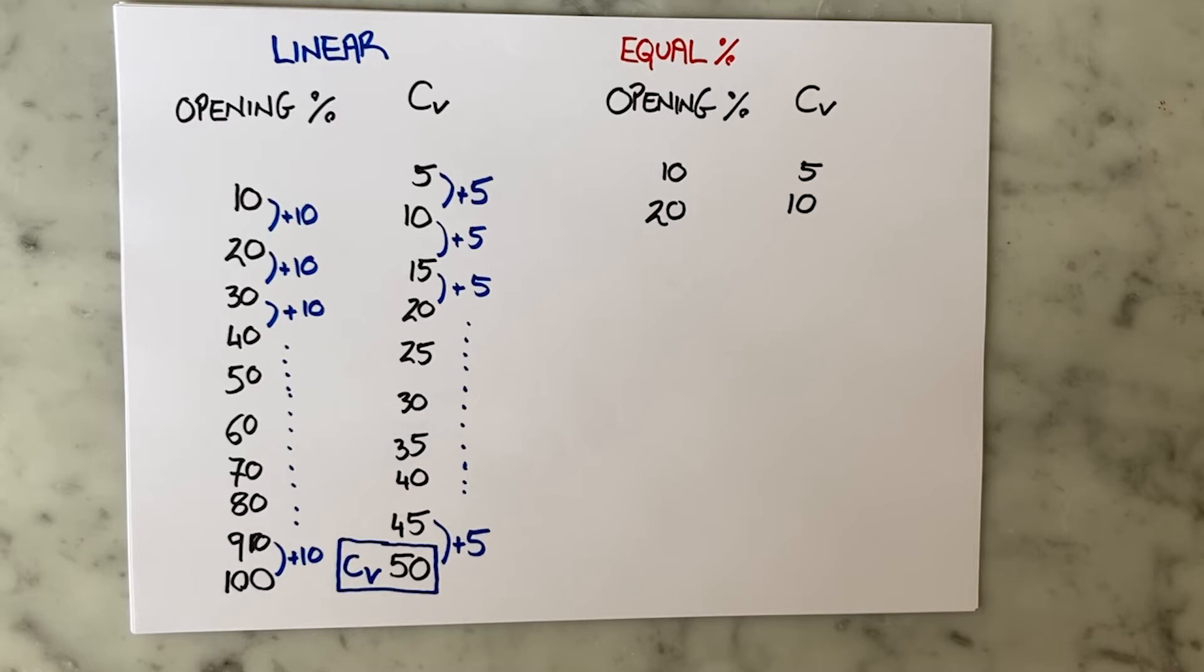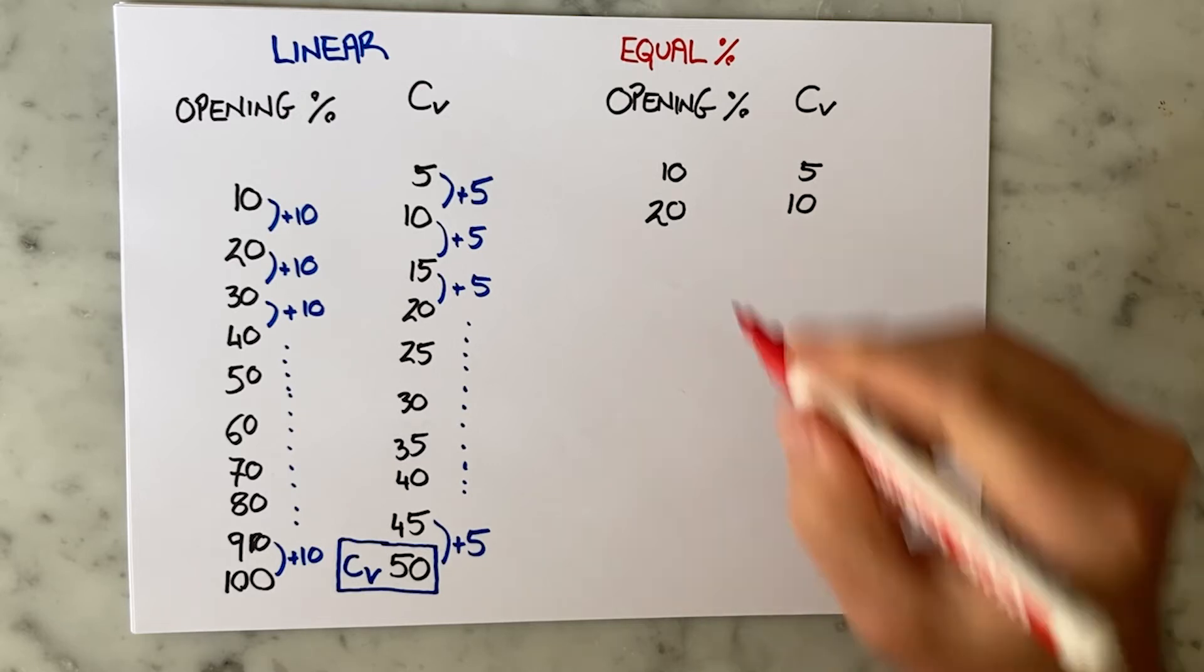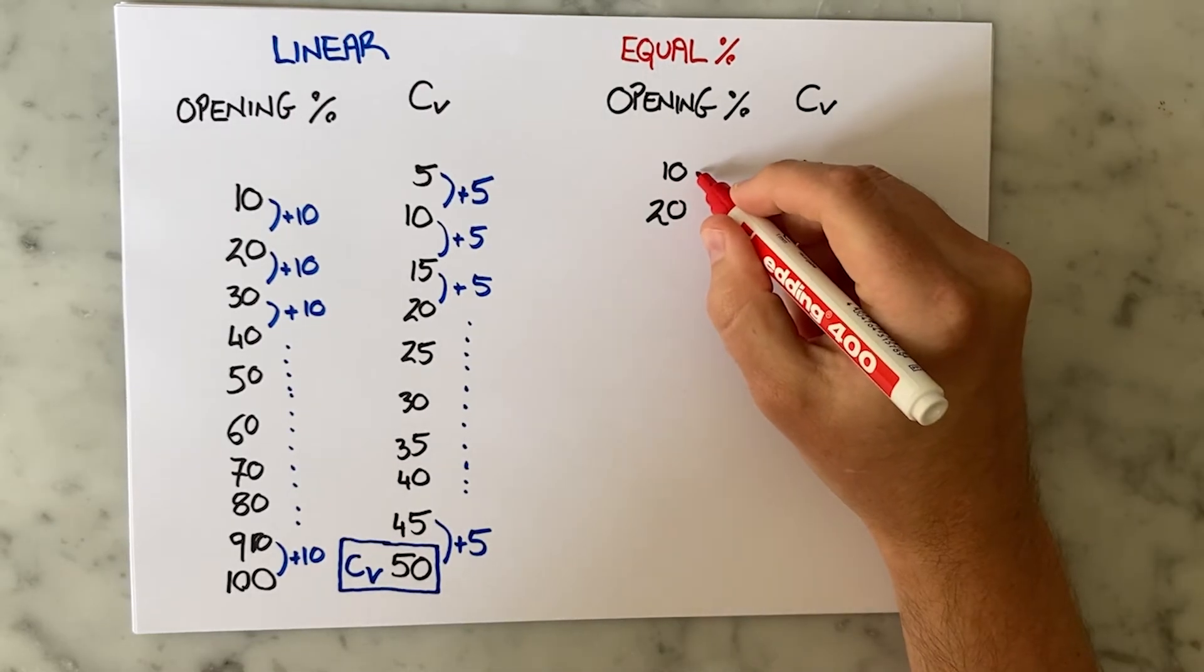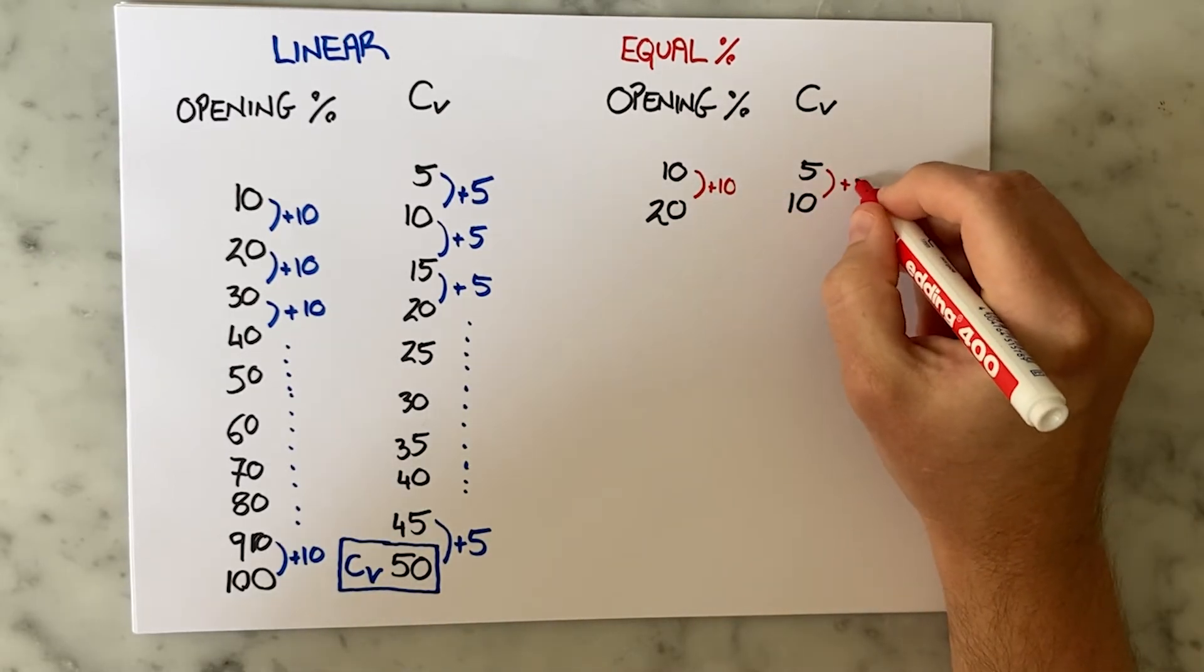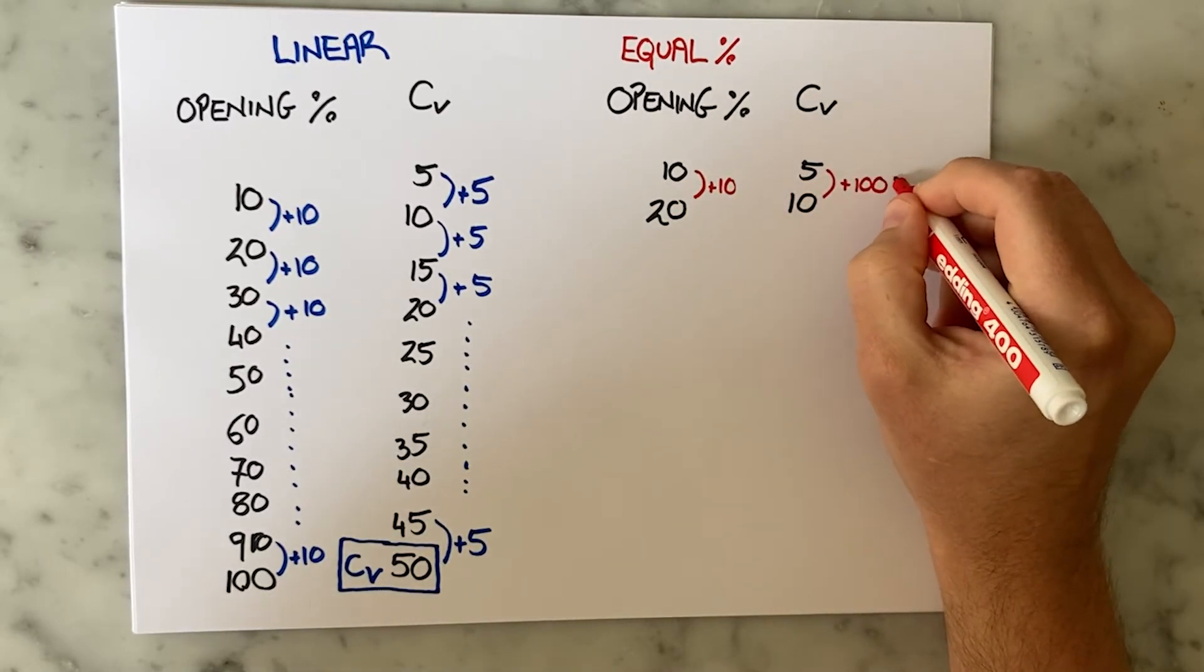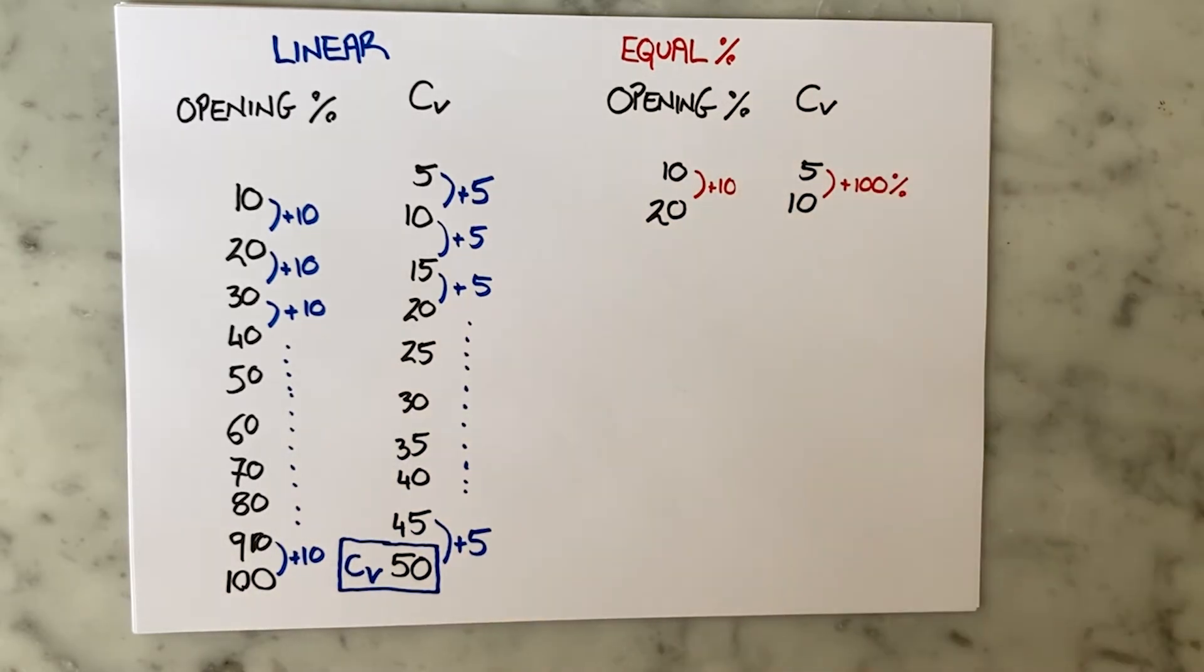Now let's look at the equal percentage valve. By definition, equal percentage means that I add the same percentage of flow for every step change in valve opening. So when I open from 10% to 20% my CV increases from 5 to 10, which means that my CV has doubled.